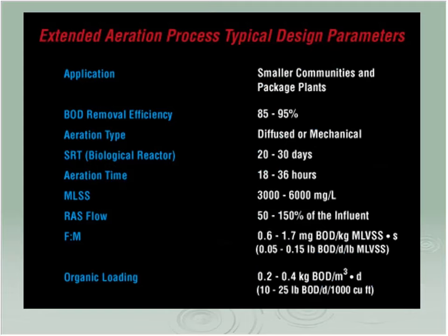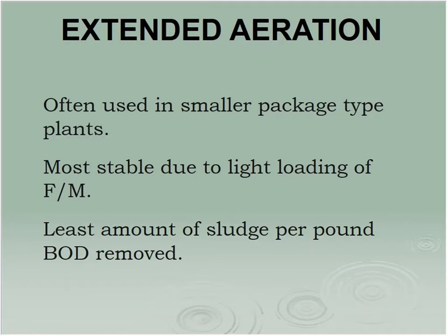The thing that's different here, you look at it, everything else looks kind of the same. 85-95% BOD removal. SRT is longer, definitely. Your aeration time is longer. But the real key that indicates to us is extended air. It's a very low food to microorganism ratio, well below the bottom 0.2 that we have in the other systems. So again, a lot of bugs, not so much food. They go endogenous, you get less sludge, they eat themselves up.